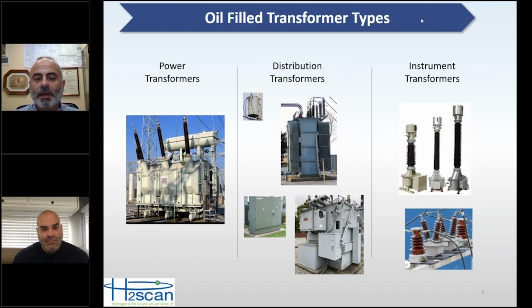So the beauty of online monitoring today, and especially hydrogen monitoring, is that regardless of the size of the transformer, whether you're talking a large transformer with 30 or 40,000 gallons of oil, or an instrument transformer with a gallon of oil in it, there are hydrogen sensors today that can help warn you and keep you in the know about the real-time health of your asset. And of course, nobody wants to wait till something fails and possibly blows up, which is what usually makes the news and usually gets people out of bed and working long hours when those things happen. And of course today you also have to worry about the environmental concerns of oil, burning oil and what's going into the environment, or oil possibly going off property, and all those different environmental concerns.